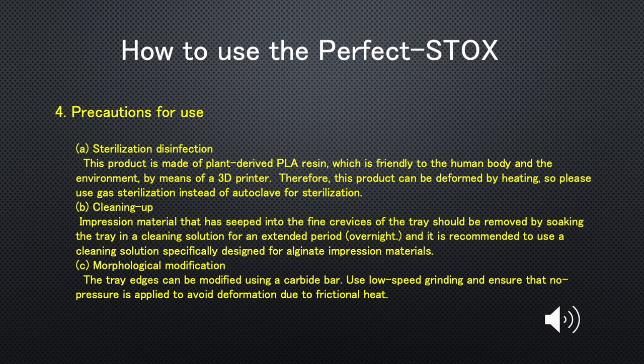Precautions for use. A. Sterilization and Disinfection: This product is made of plant-derived PLA resin, which is friendly to the human body and the environment, produced by means of a 3D printer. Therefore, this product can be deformed by heating, so please use gas sterilization instead of autoclave.